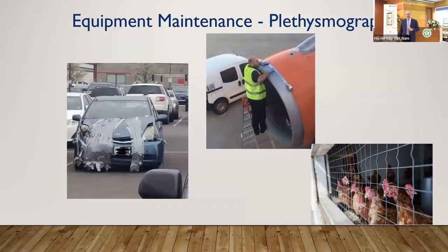So we don't do maintenance on our equipment with duct tape, and we don't do maintenance on our equipment with chicken wire. We do maintenance on our equipment with the manufacturer's recommended processes and pieces of equipment. I bring this point up because I have gone into laboratories and their body plethysmographs have been fixed with duct tape.